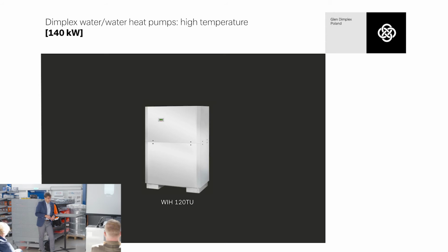I need to tell you that today we are finishing a very large project in Poland with these heat pumps. We are building a cascade of 12 devices. It gives a total output at the level of 1.5 megawatts, so 1,500 kilowatts output. It is a district heat supply. This big plant will support several surrounding buildings, and we will warm up the water up to more or less 70. But the down heat source is geothermal water taken from the earth.